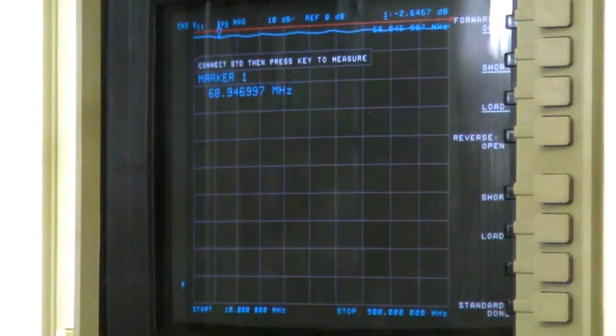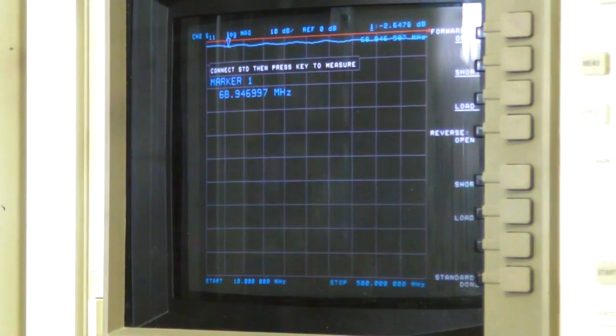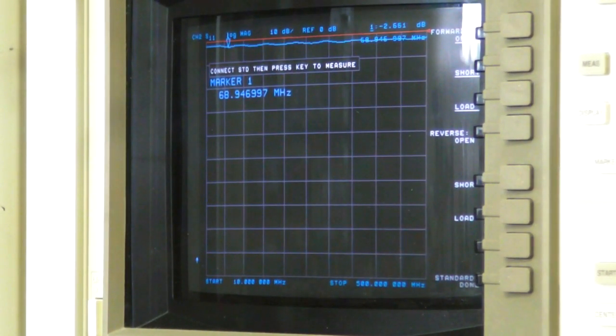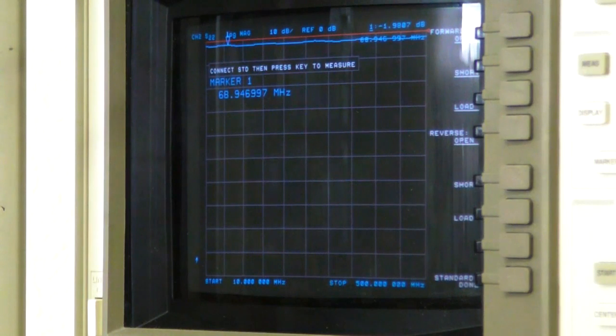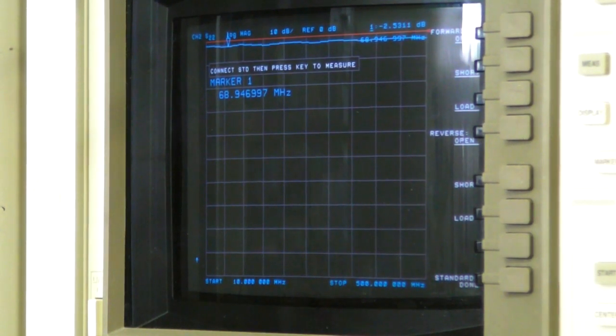Then we'll do the other port here. We'll show port 2, the open first. Anyway, it builds this fancy 12-term model with amplitude and phase at the 201 frequencies that it's observing. Since I'm trying to go as quickly as possible here, we've limited it to 201 points. The instrument has enough memory to do 1,601 points maximum.